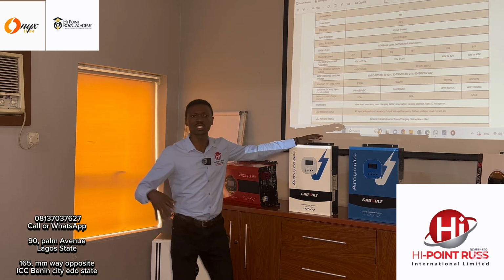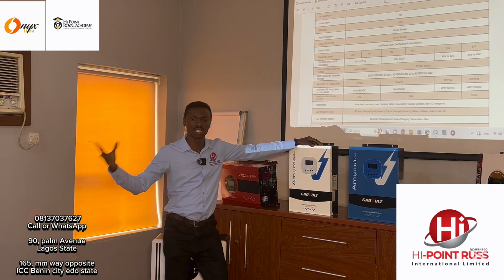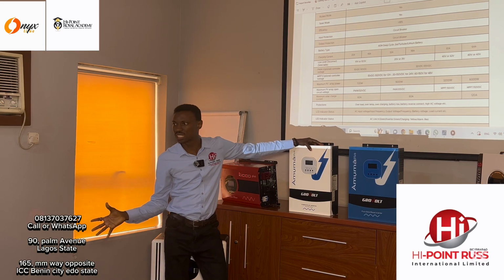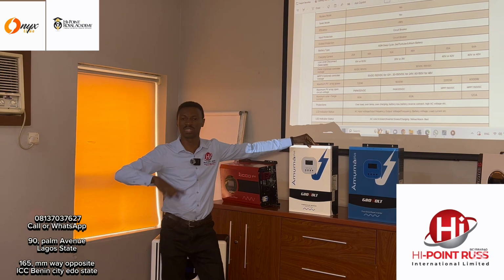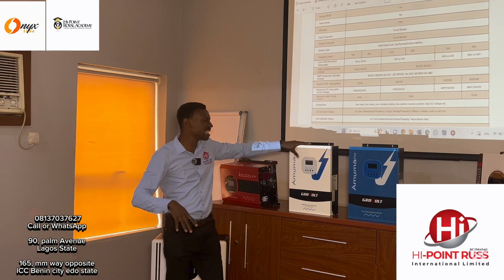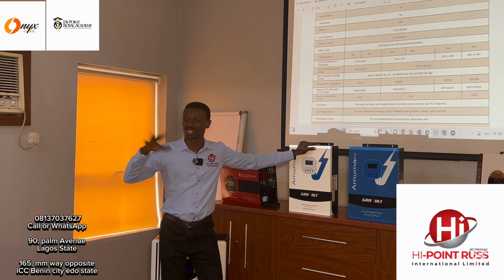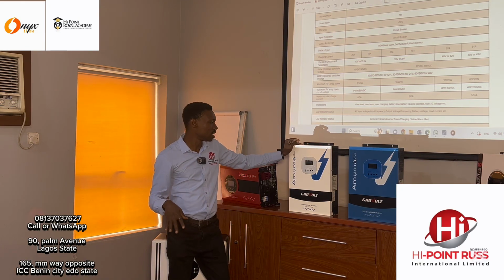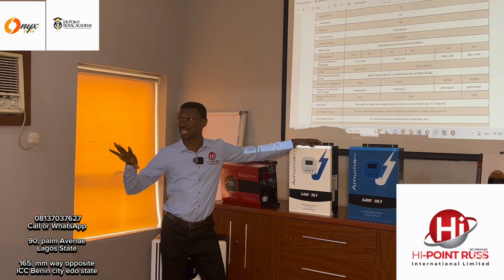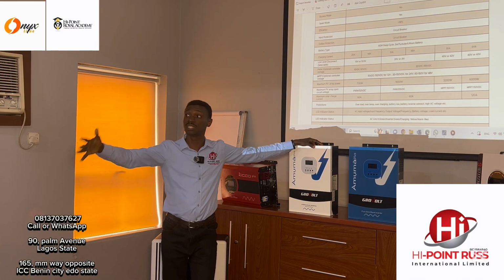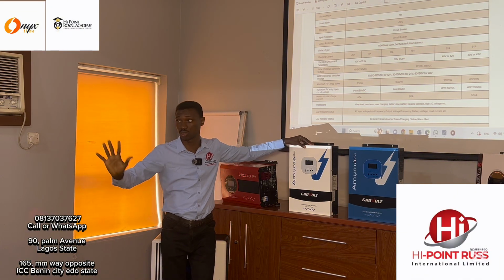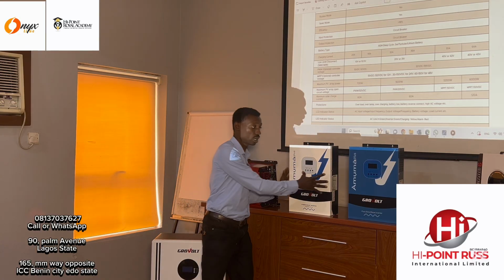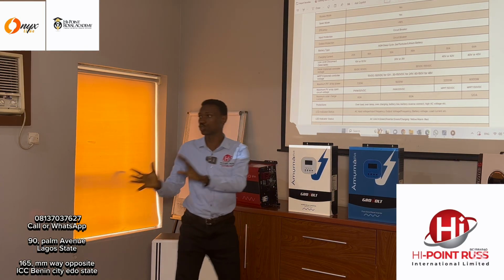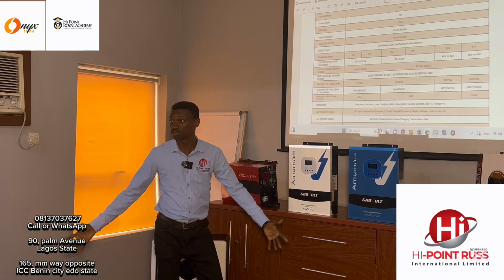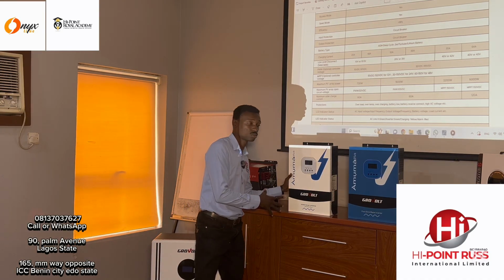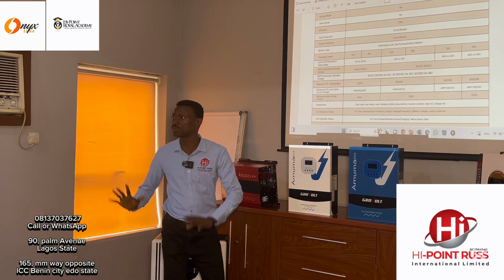Yes, but in a case where somebody, maybe due to funding, doesn't have so much, or in an upgrade scenario, has this and wants to use a lithium battery - whatever the case, it will work with lithium in the sense that if that battery is depleted, it will take the exact voltage. As long as if this is a 24 volt inverter, you give it your 24 volt lithium, it's fine. If it's a 48 volt inverter, you give it the 48 volt grade lithium, it's fine.